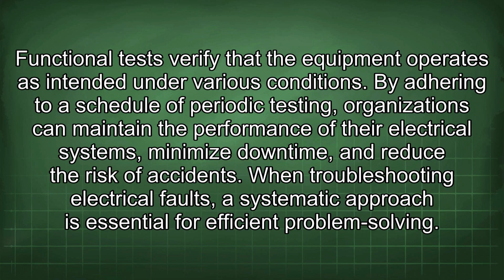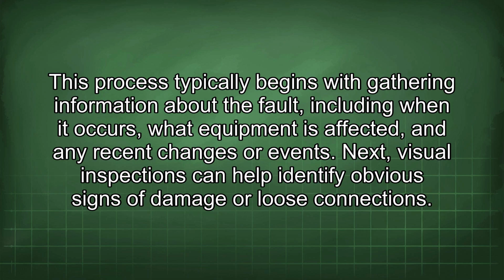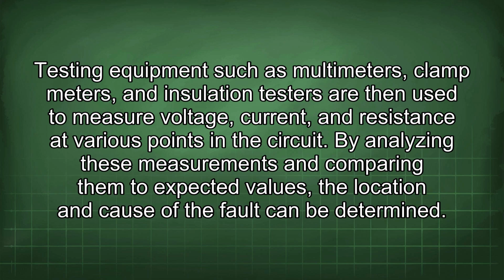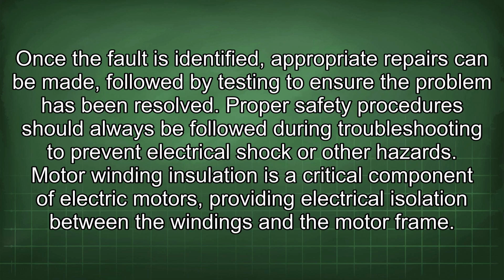When troubleshooting electrical faults, a systematic approach is essential for efficient problem solving. This process typically begins with gathering information about the fault, including when it occurs, what equipment is affected, and any recent changes or events. Next, visual inspections can help identify obvious signs of damage or loose connections. Testing equipment such as multimeters, clamp meters, and insulation testers are then used to measure voltage, current, and resistance at various points in the circuit. By analyzing these measurements and comparing them to expected values, the location and cause of the fault can be determined. Once the fault is identified, appropriate repairs can be made, followed by testing to ensure the problem has been resolved. Proper safety procedures should always be followed during troubleshooting to prevent electrical shock or other hazards.